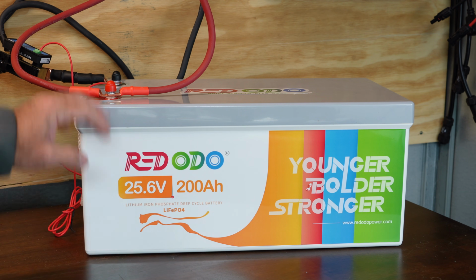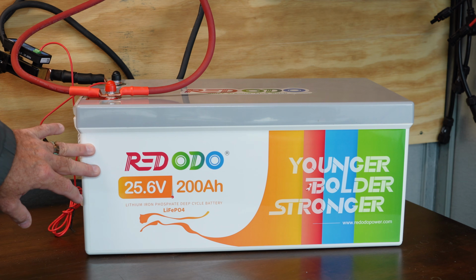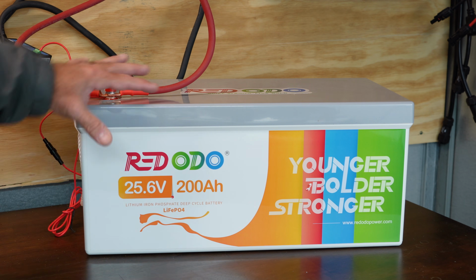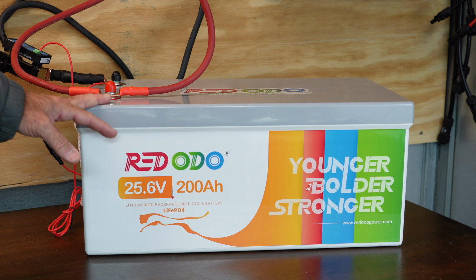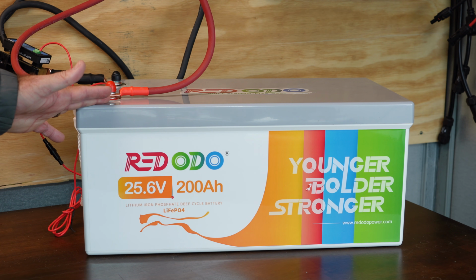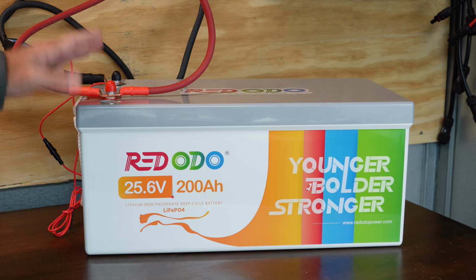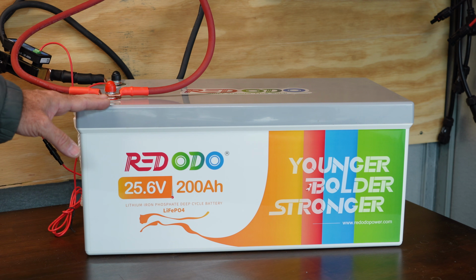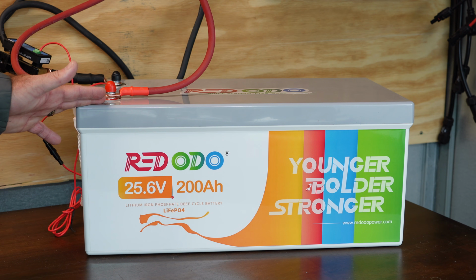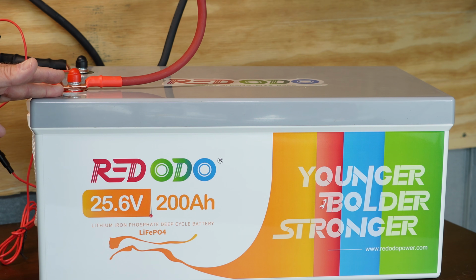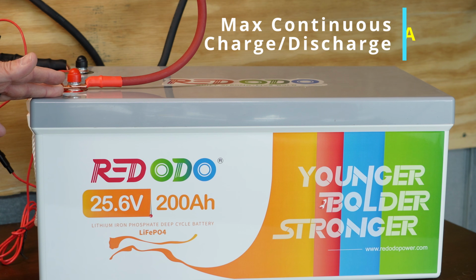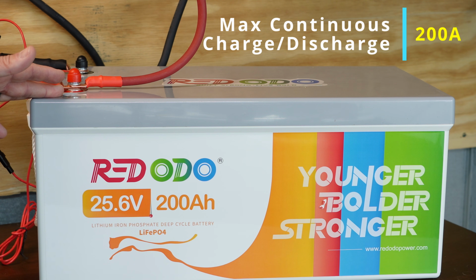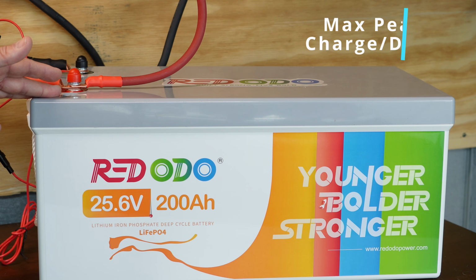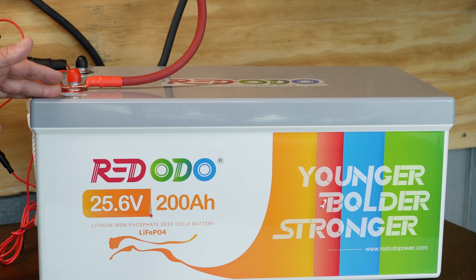Being a 200 amp hour battery, this one comes with a 200 amp BMS. I've got some stuff hooked up here — actually two different inverters at the same time, a 3000 watt and a 2500 watt 24 volt inverter, because I don't have a single inverter that can pull 200 amps at this point. So I had to get a little creative to test this, which we'll look at in a minute. The BMS is 200 amps, and its maximum continuous charge and discharge rate is also 200 amps as a result. But it will allow you to discharge for up to 5 seconds at a max of 400 amps, so you can really get some serious output from this single battery.